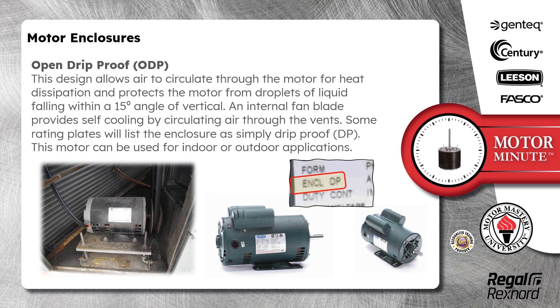Open drip proof, ODP. This design allows air to circulate through the motor for heat dissipation and protects the motor from droplets of liquid falling within a 15 degree angle of vertical. An internal fan blade provides self-cooling by circulating air through the vents. Some rating plates will list this enclosure as simply drip proof, DP.